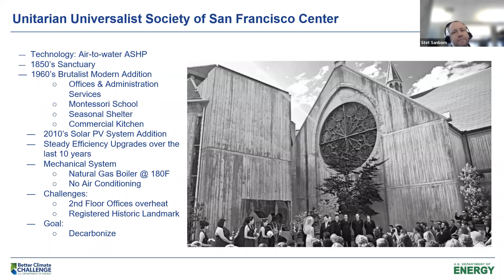As we approach a project, especially retrofits with heat pumps, there's a dream list we'd like to go through that involves deeply understanding the energy use and hourly demands for the building, then going through recommendations around efficiency measures before we get into equipment selection. Our dream is to get the loads under control before picking equipment, because if you just try to do a hot swap of a boiler straight to a heat pump, you're likely going to run into cost barriers. One key thing we can do for both life cycle improvement and greenhouse gas emissions reductions is right size that equipment, focusing first on efficiency measures.